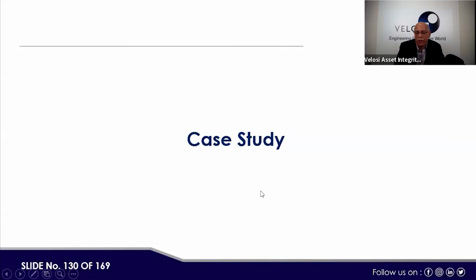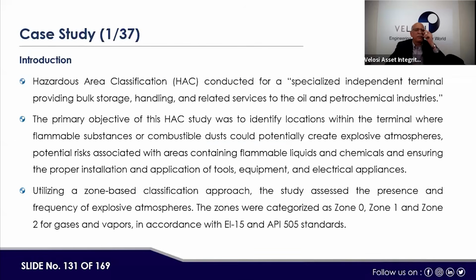So now, what we covered up to now is the hazard area classification, and after hazard area classification, we saw the effect: how the electrical and instrumentation equipment are selected and how their protection class, gas, surface temperature, and EPL level are defined. Accordingly, that information is printed on the nameplate and specifications are also updated. All the tests and certification are done as per that applicable class, and then that applicable class equipment is installed into the respective HAC area. So this is basically the use of the hazard area classification and its impact on the selection of instrumentation and electrical equipment. Here I will be a little fast because it's a case study.